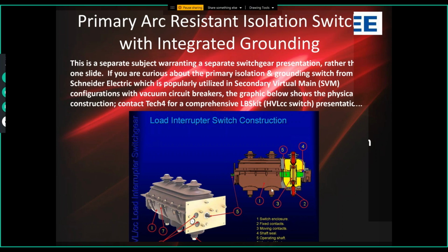Mike, what's the AIC rating of that switch? What's the what? AIC rating, amps and AIC. Oh, great question. That is a limitation. Not only the AIC rating, but the current rating. Like all switches at medium voltage, only 2 flavors, right? 1200 amps and 600 amps, and the AIC rating 25 kA. So that's a great question. If you have a medium voltage environment that's above 1200 amps or greater than 25 kA, that doesn't work for this. That is the greatest electrical limitation of using these switches.